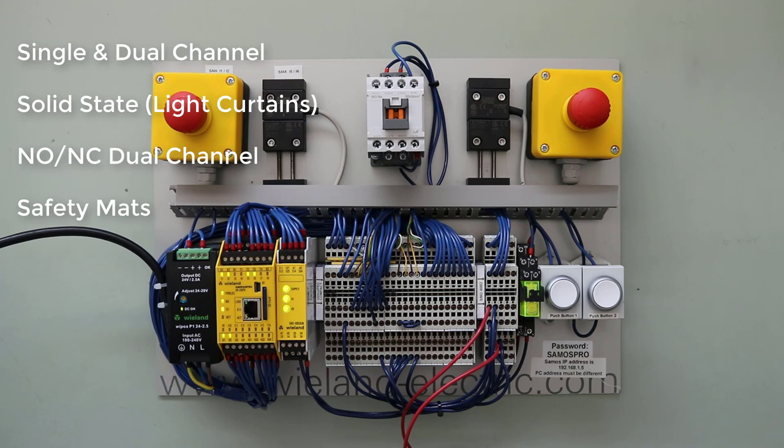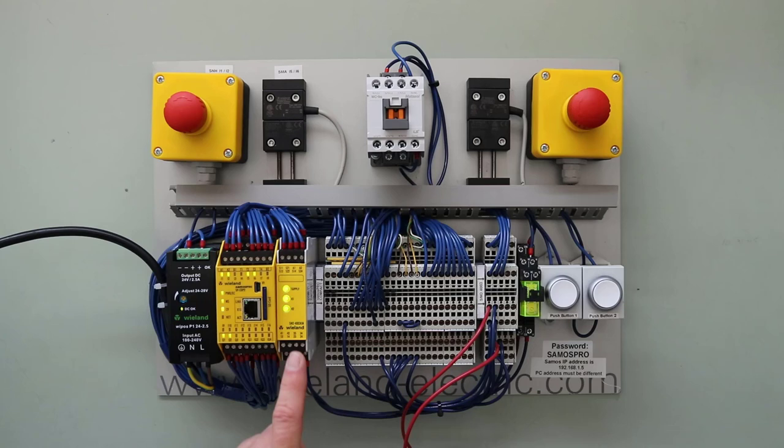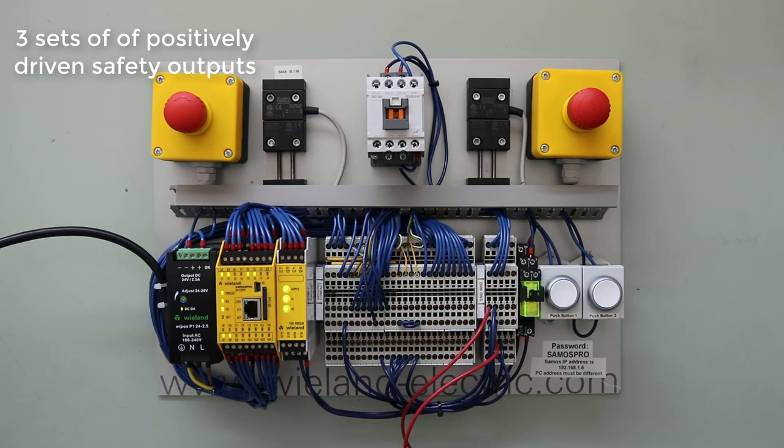Most other manufacturers who produce safety relays in this size package would require different part numbers to accept those different types of input signals. The Wieland Universal Safety Relay has three sets of positively driven safety outputs and one set of non-safe annunciating outputs.